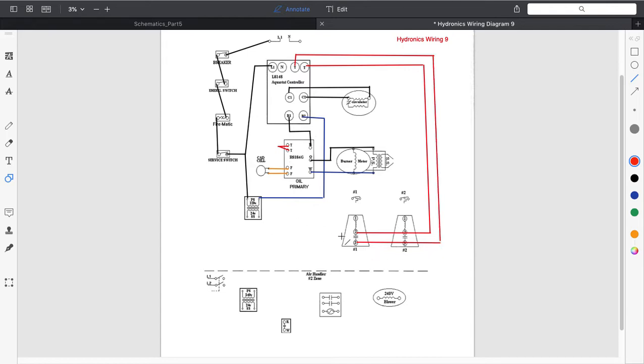Okay, so my zone valve end switch is tied in. Now, because pin 2 is actually the common for the motor as well, I need to tie in one side of the transformer to this as well. And I'm going to pick on that side because it just makes the most sense. So we're going to come ahead in over here, and we're going to tie that transformer in.